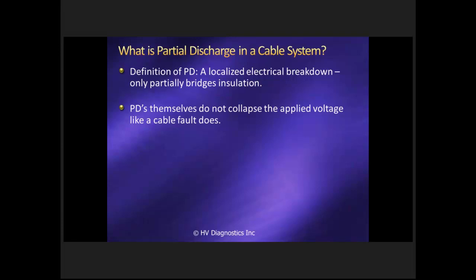So if you pick up PD in a cable, don't expect to go and hook your thumb onto the cable and find the fault. It's not going to be there. Don't expect that your relay protection is going to see the fault either. PD is a very, very small signal that is generated inside the cable. They are singular events, so you don't just look at one event, you look at them statistically. If you have a discharge in a splice, you'll be looking for a number of discharge patterns coming from that splice.